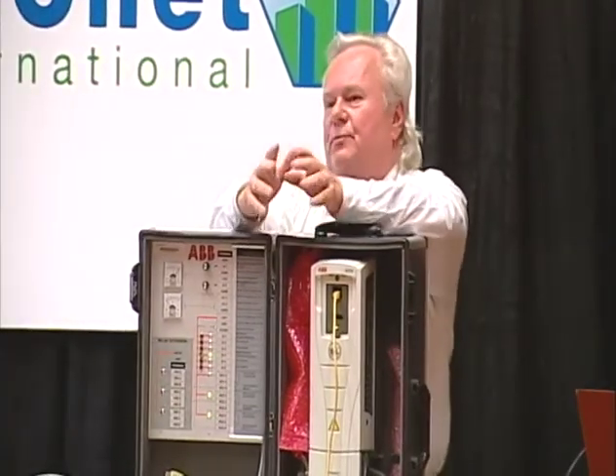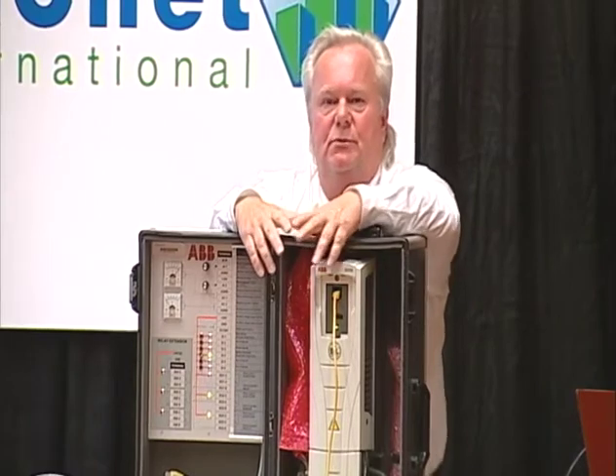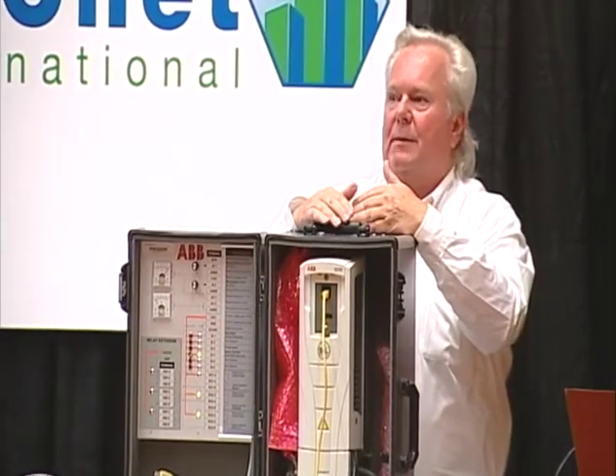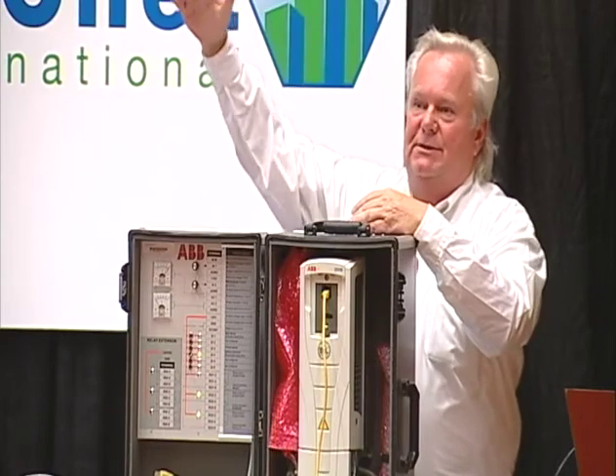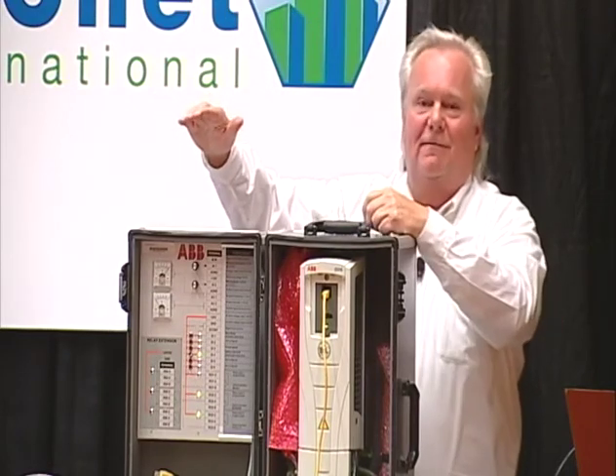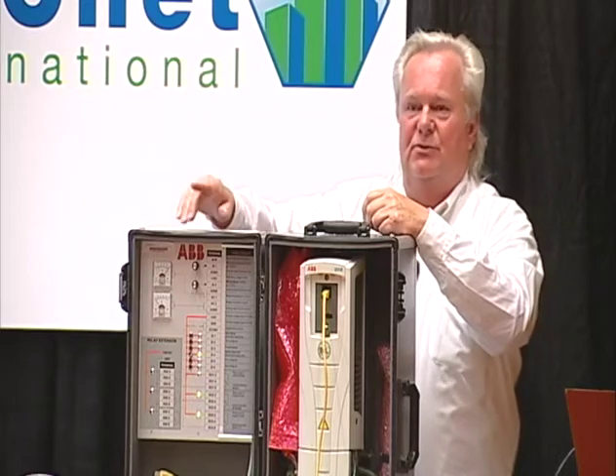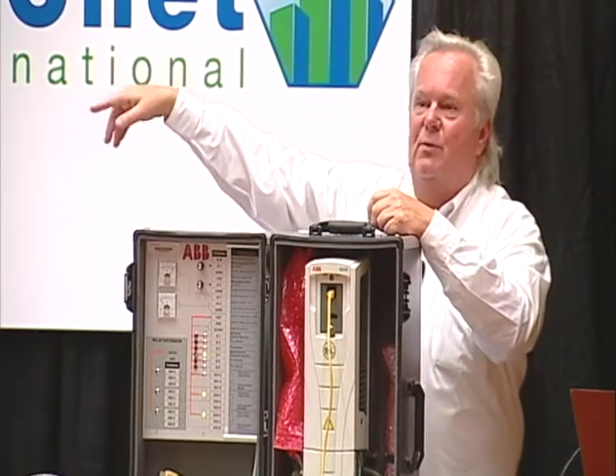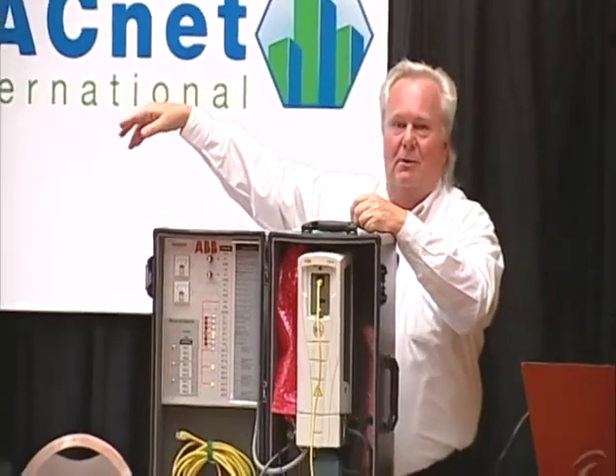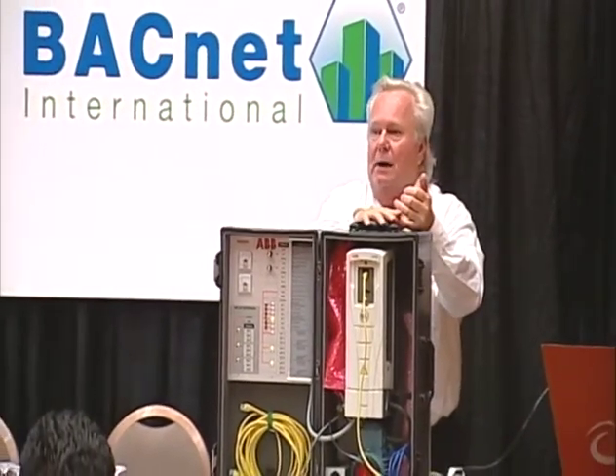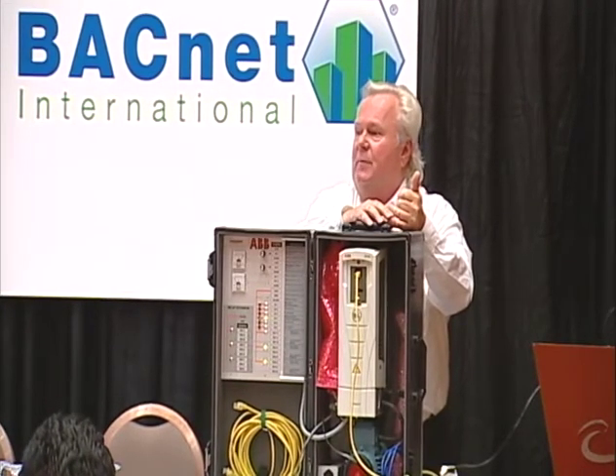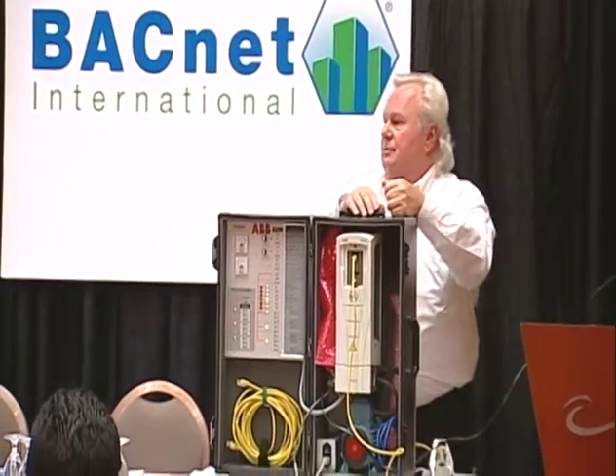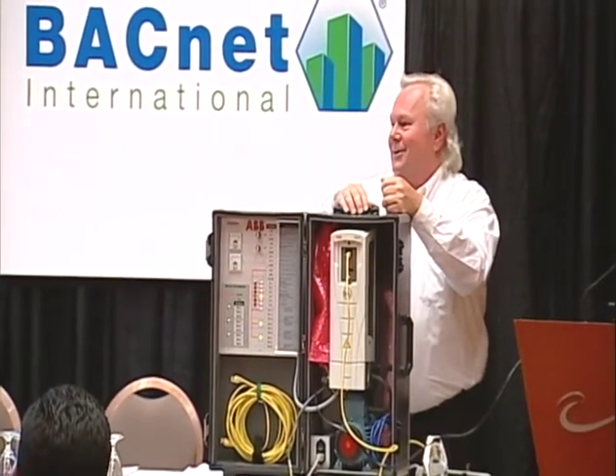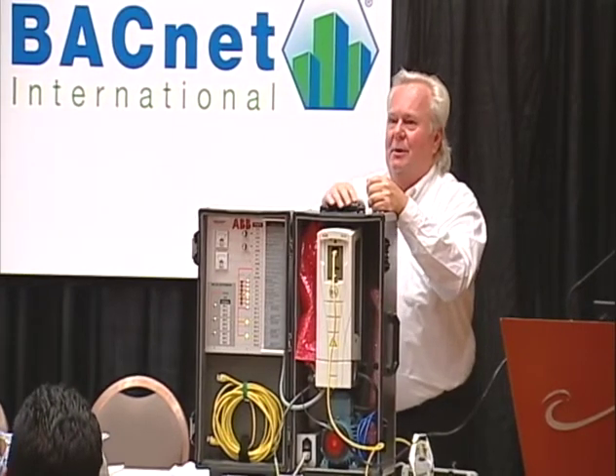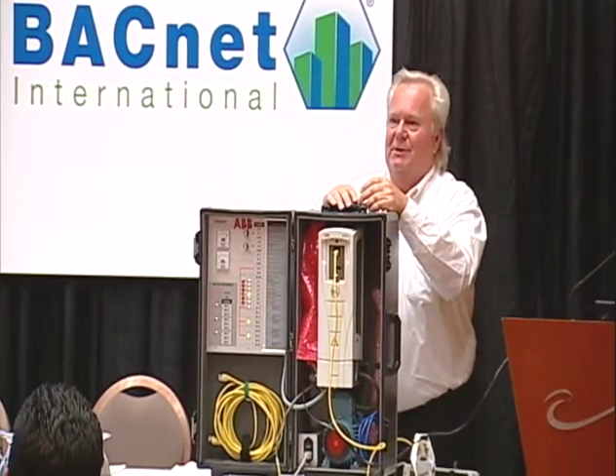So what modern variable frequency drives have built into them is called sleep and wake up. I can program the drive that if the temperature gets down below my set point, to turn itself off. And if temperature continues falling, I can start modulating that three-way valve and bypass the water around the tower. So I go into a free cooling mode for a while, and then I don't want too cold of water going back to the chiller. So if the temperature feedback continues falling, I simply start bypassing the chiller or the cooling tower until my bypass valve is completely modulated, and now I'm not sending any water.